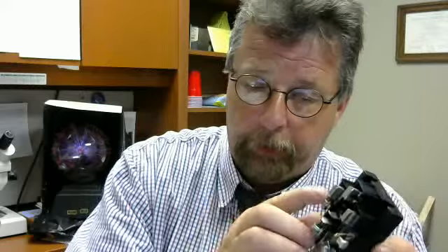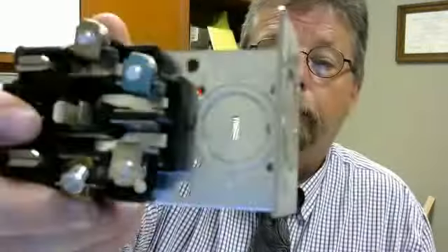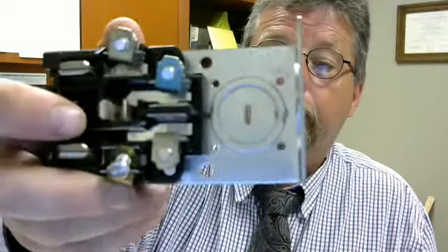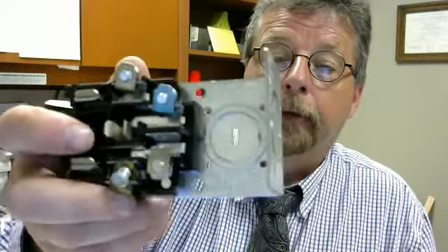They all have a temperature rating, they all have a withstand rating, and so there's only a certain range of wire that you can apply here. And that data is given on the equipment as well. I don't know that that's going to focus, but it's in there. You can see that writing back there tells us what we're allowed to utilize for that.